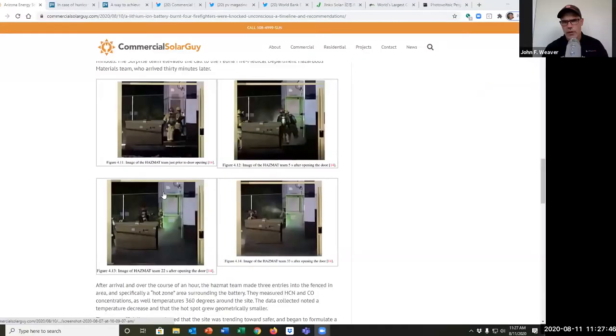At the end of that period, with the utility representative on site, they decided they needed to look inside the battery, inside this shipping container structure. They opened the door, and that's the series of 4 pictures you saw. First they opened it and looked for fire. There was nothing. They put hardware inside to measure the chemicals in the air and got a reading, then put in temperature measures. All these events happened over about 33 seconds, in the order shown in that image, taken from a video set up to record the event.